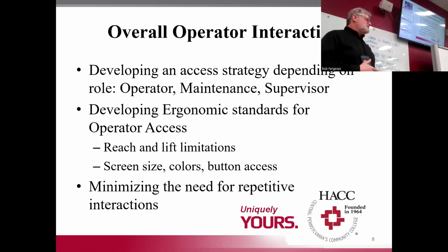Another few aspects of HMI are the mental aspects. Not really mental, we'll call it visual and mental. Anyway, some people are colorblind. And often it's red-green colorblind. So if you make something red and you flash it green, a person with red-green colorblindness will never know it flashed green. They will be completely unaware of that. So colorblindness is something else you need to allow for.